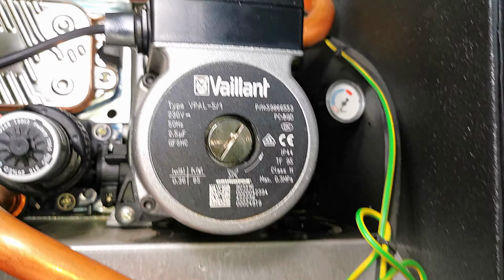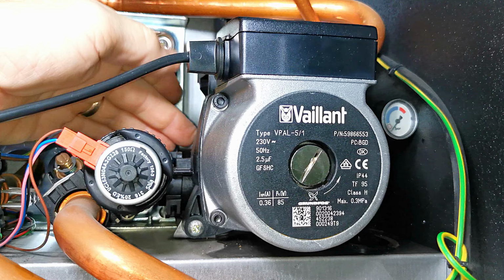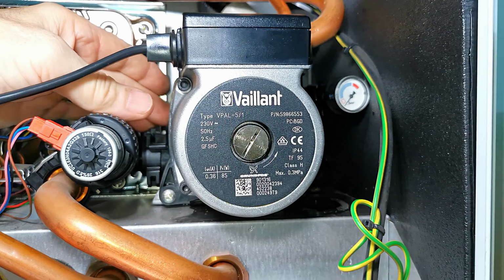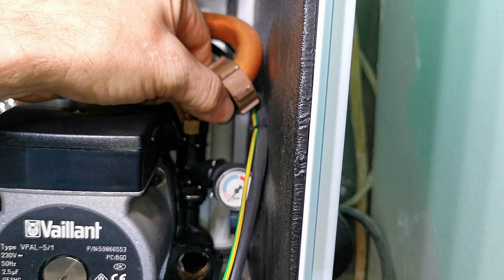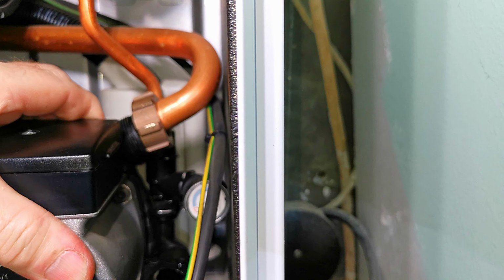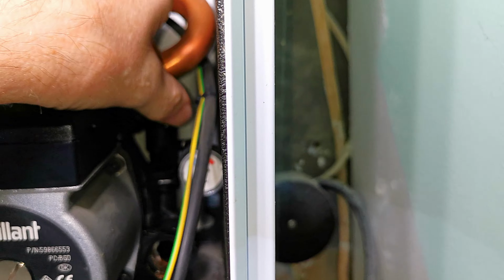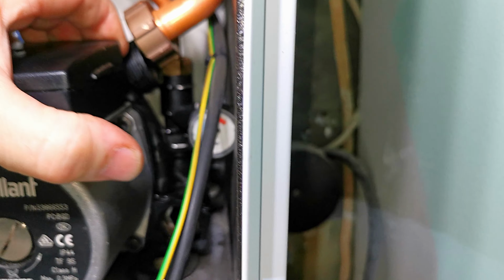I'll now push the pump sideways to the right, giving it a little bit of a wiggle to release it from the diverter valve. At the same time I want to make sure I lift this pipe up and out of the way so the pump can move to the right hand side. And there we go, the pump is now free and moved away.